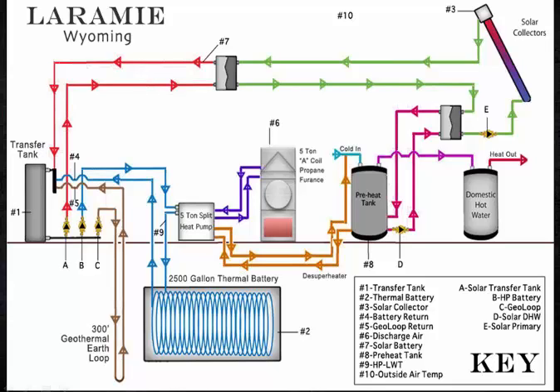So that's the basic configuration of how it works. Transfer tank is the point where all the energy integrates, and the solar collector or the ground loop can contribute energy into the system, and the battery is this big thermal moderator that allows a 5-ton to run, because obviously you can't run a 5-ton heat pump off of just a 300-foot loop. It wouldn't be nearly conductive enough.